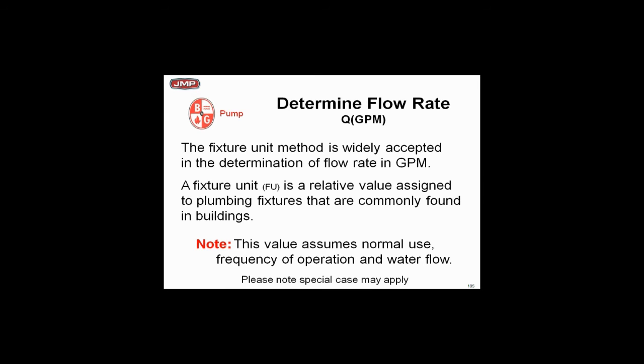Those values assume normal usage and we're going back again to the fact that if you've got a cooling tower or you have body showers or some special amount of water going in there, the fixture count would be too light, would not be enough flow. So what we're going to have to do is make sure if you've got special cases that you add to your fixture counts, any body showers, any cooling towers, any special water usage, because what goes into a building has to come out.